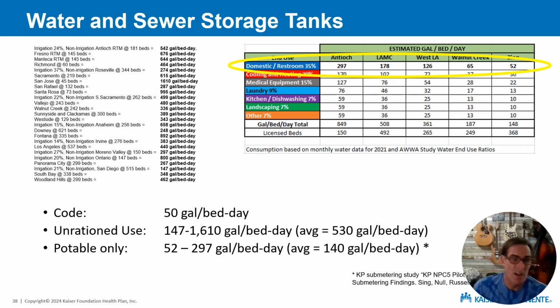In particular, if you don't shut down your cooling towers, then you're at a lost cause almost immediately. For anyone who doesn't know, the cooling tower water use is usually a lot more than the potable water use. So again, just because we have something in the code, it doesn't make this wise, right? This really is kind of a false sense of security that's provided within this measure.